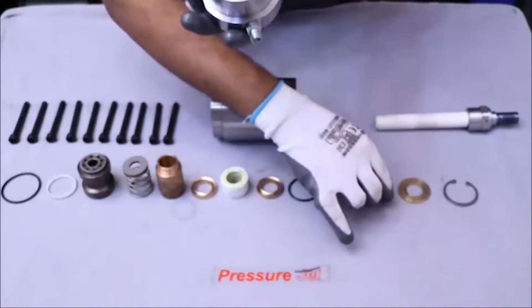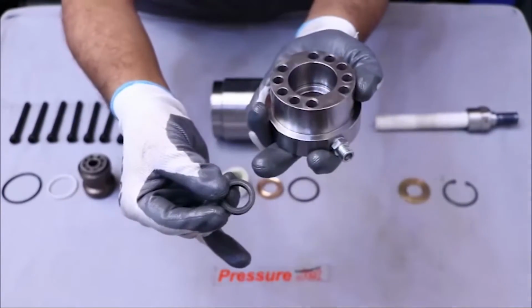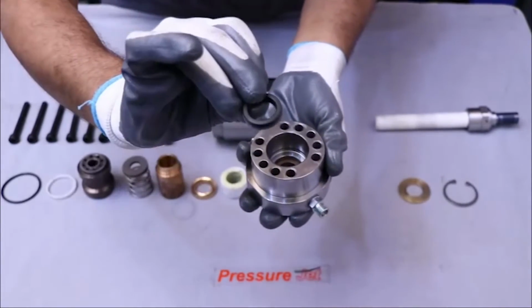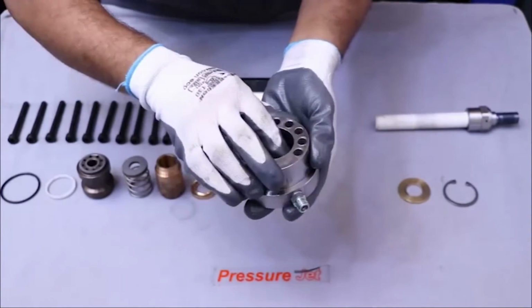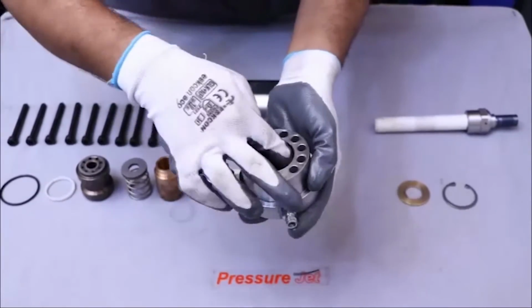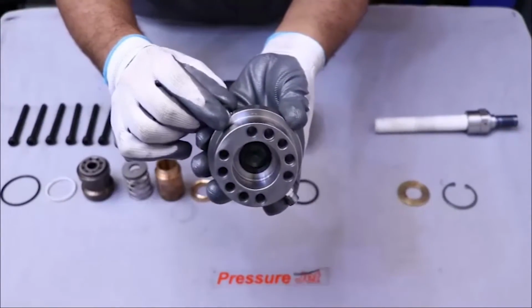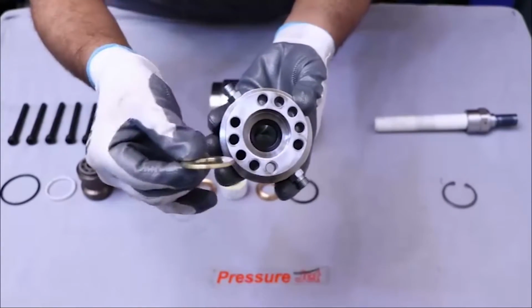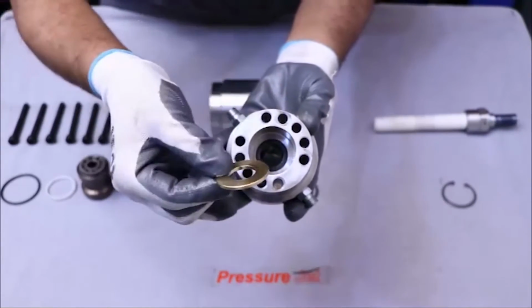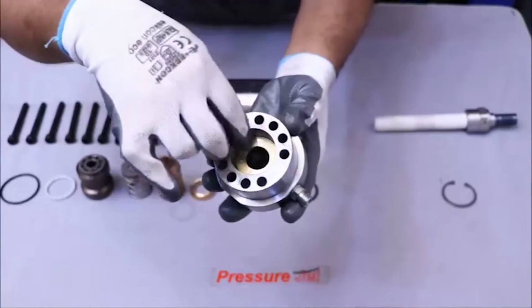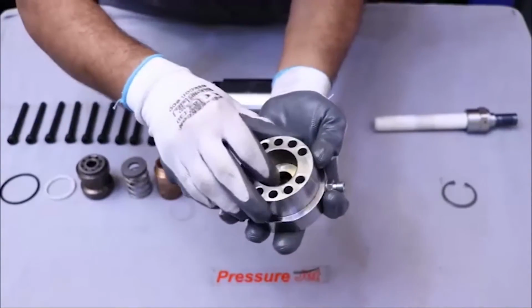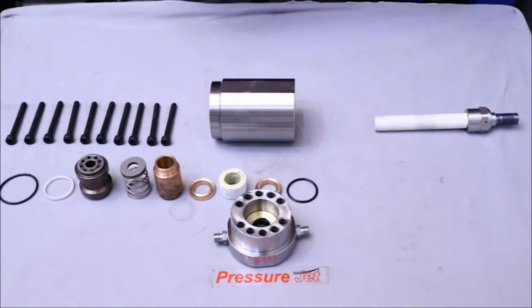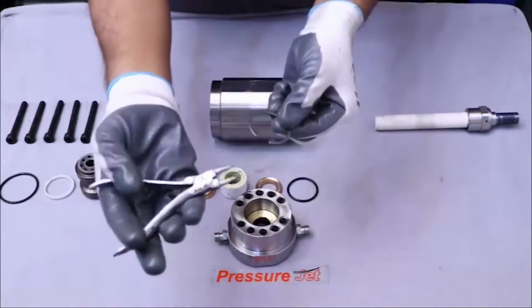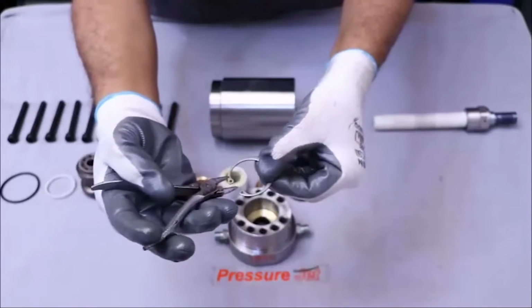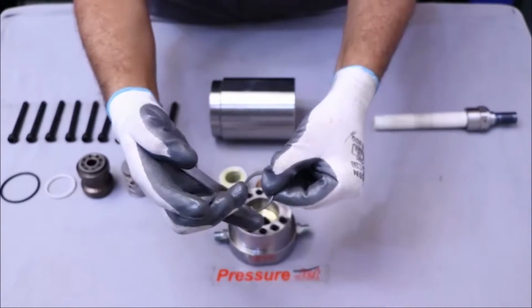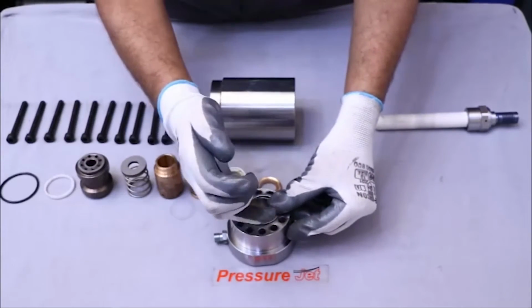After that, assemble the low pressure seal inside the stuffing box cover and check that its flat surface faces upward. After that, take the scraper ring and place it on the low pressure seal in the stuffing box cover. Now take the circlip. Using circlip pliers, place the circlip inside a groove. During installation, make sure that it is fitted into its groove.